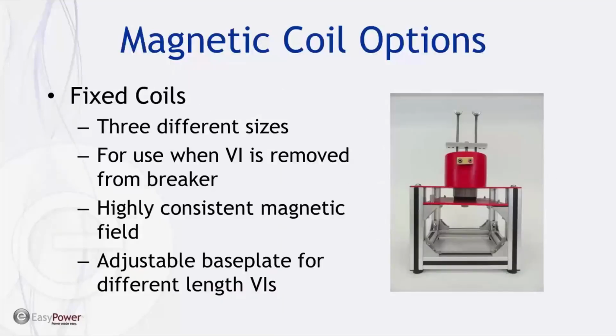We also have lab-based coils or shop-based coils. If you are a service shop or you have the vacuum interrupters removed from the circuit breaker often, then this would be a coil that would make the test much easier. You don't have to wrap it. You simply open the contacts of the vacuum interrupter and place it inside of this magnetic field coil.